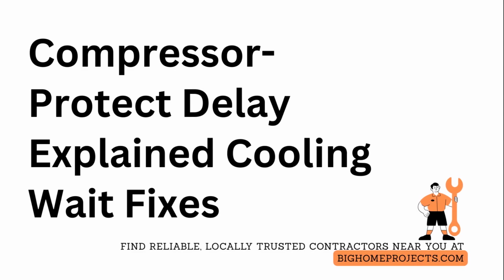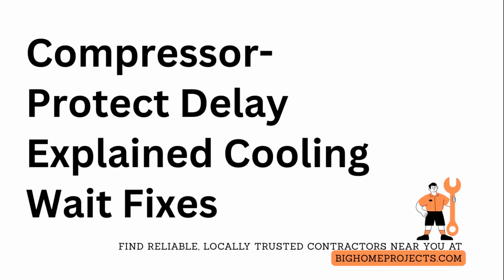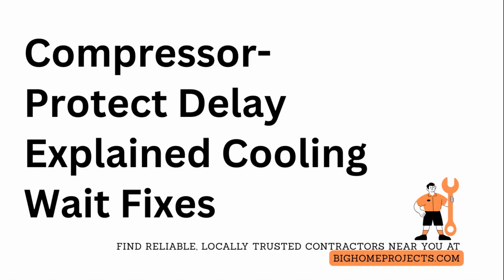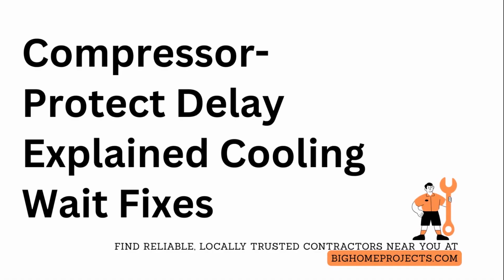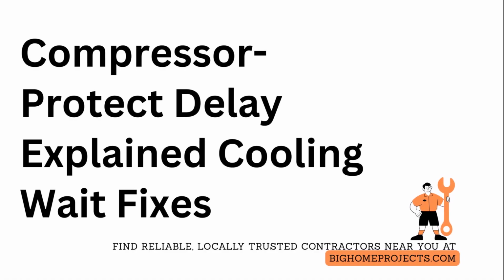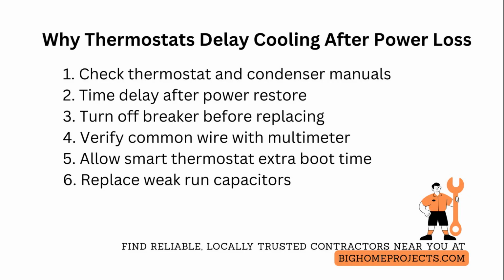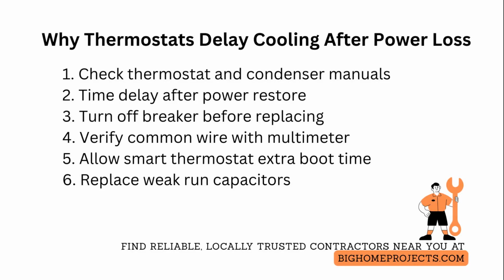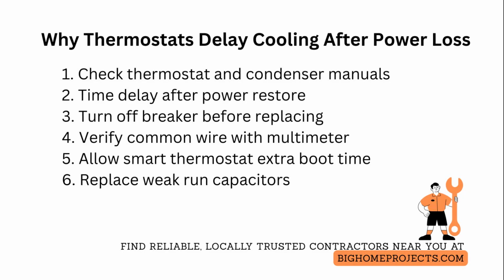Power interruptions can cause a built-in safety delay, so your thermostat will typically wait about 5 minutes after power is restored before it turns the air conditioning back on. Most modern thermostats include a Compressor-Protect delay that prevents short cycling and protects the outdoor unit. That delay is commonly around 5 minutes but can range from 1 minute to 15 minutes depending on the model, fan and compressor type, and manufacturer firmware.